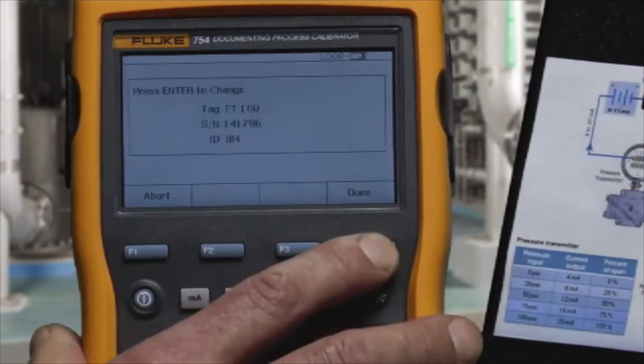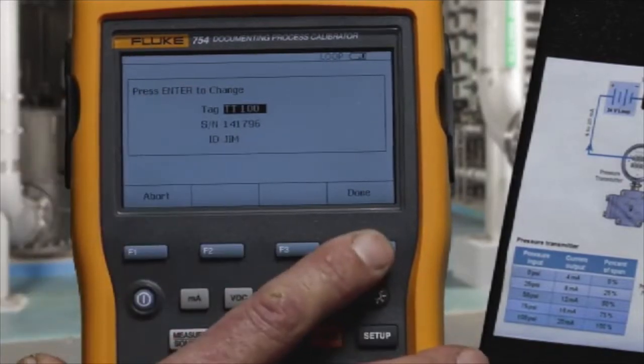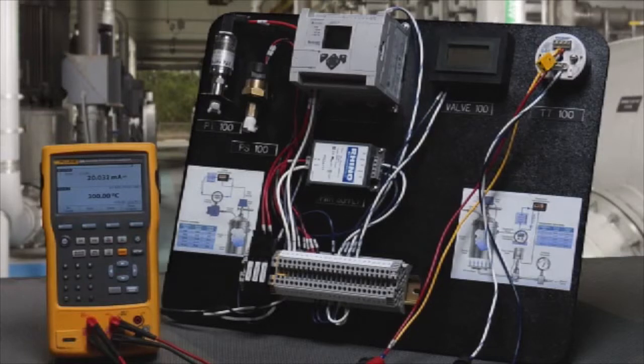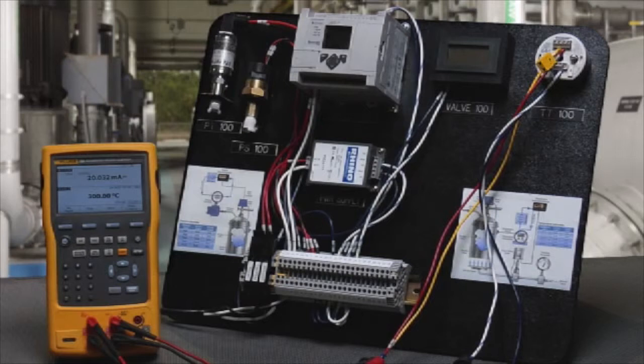It's done. Tag serial number and ID of who did the work. We're done because it passed the test, and we have completed documenting the performance of this RTD transmitter using the 754 documenting process calibrator.